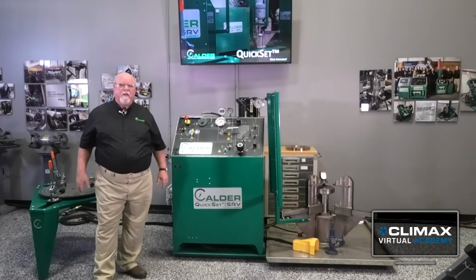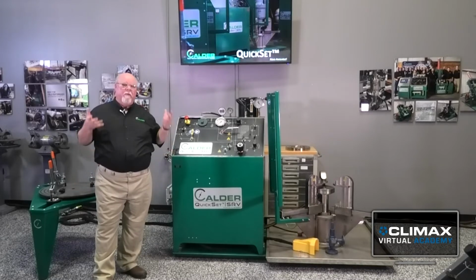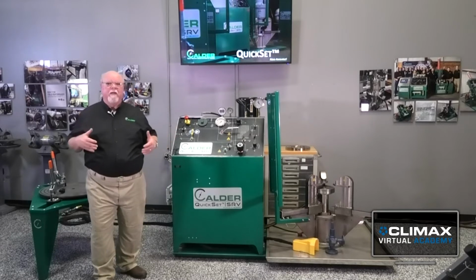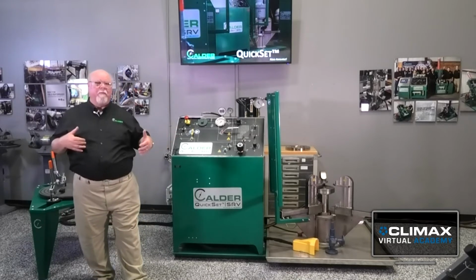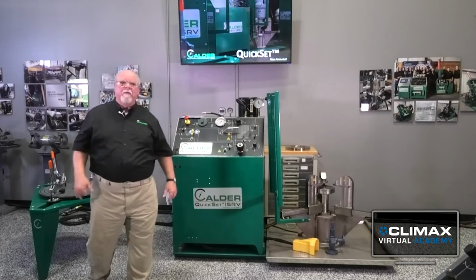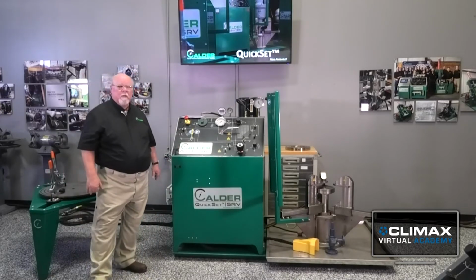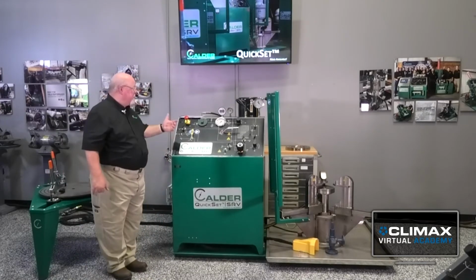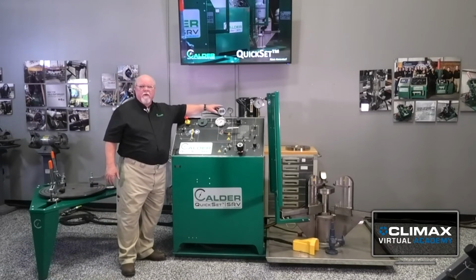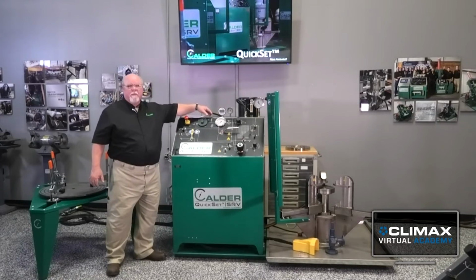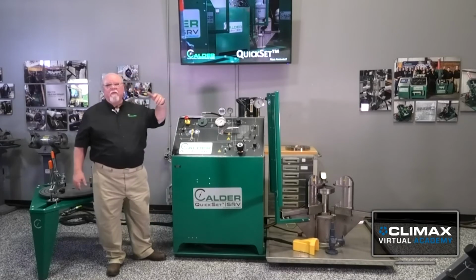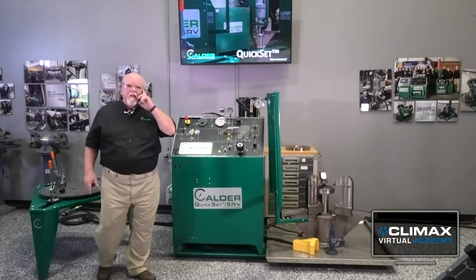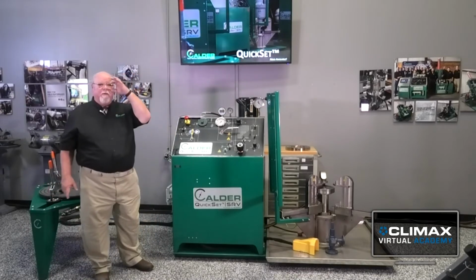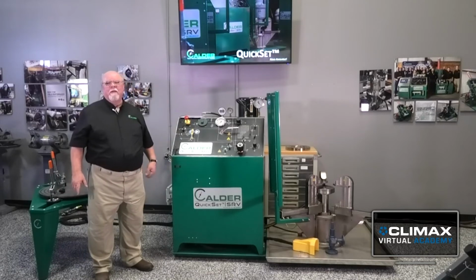Oftentimes that comes into play with the larger valves, or when you're testing for liquid. You want to be able to put more and more water into the vessel and give you a longer test frequency between having to refill the vessel. Another option is a digital gauge upgrade for testing. This particular unit has a max setting, so when you're running your test, you can check to see what the maximum pressure was or determine what your set pressure is on your valve.